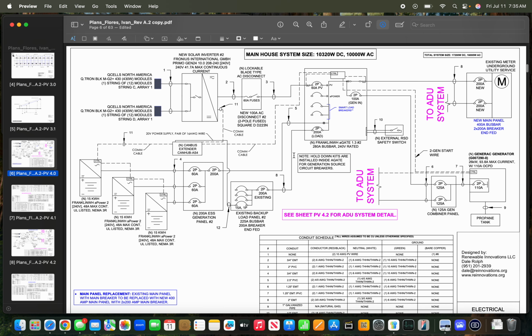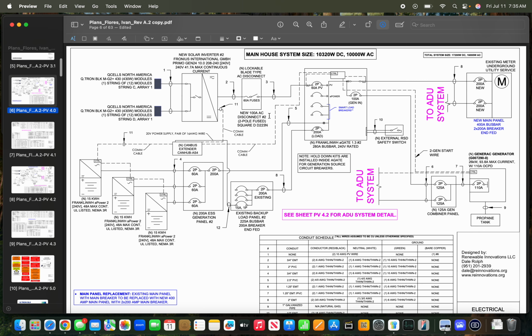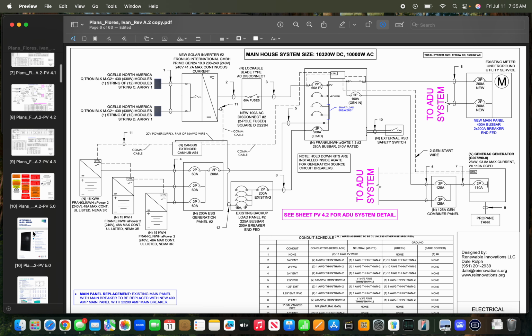Which it wouldn't be anyway, because it's hitting the inverter right there. They also won't have to worry about any AC energy coming over to the house, even without having to run 400 feet down to pull those disconnects. Those disconnects are down there along with the ones for the batteries, so if something near the equipment needed first responders to shut off, they'll be able to quickly shut off all these devices one by one.